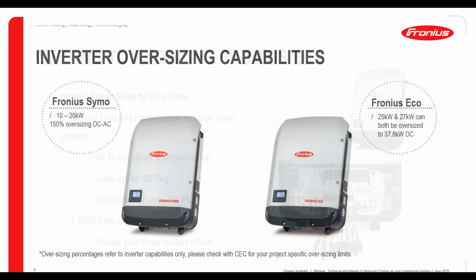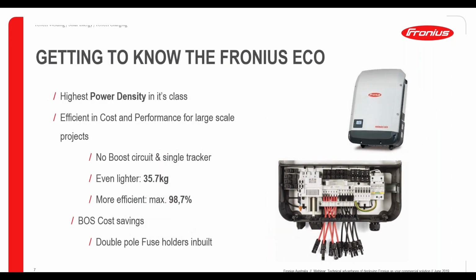Now, in terms of the two different types of inverters, the Fronius eco is quite unique in that sense. All of the other inverters, the Primos and Symos mainly, have two trackers and a DC boost circuit. However, the eco is a little bit of a different beast, so we thought we'd touch on that firstly. Efficiency wise, if you do hit the sweet spot, it can end up being one of the more efficient inverters. It doesn't have a DC boost, as I mentioned, so the DC voltage window is going to start off a lot later than a typical inverter that you'd be used to in the industry. And you do have a single tracker, meaning that there has to be symmetrical strings connected to that same tracker. On the other side of it, the cost saving side of things that we'll touch on as we go along, there are inbuilt fuse holders, but I'll touch on that a little bit later.